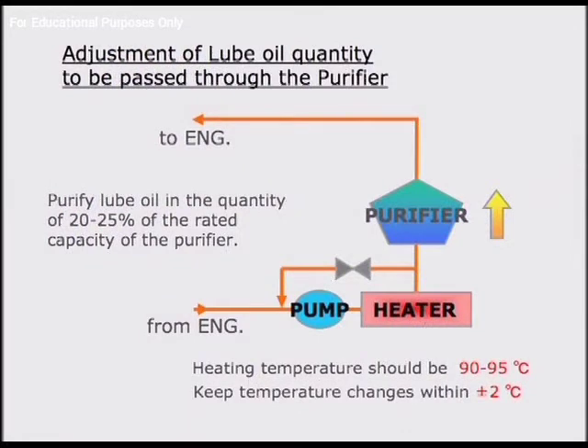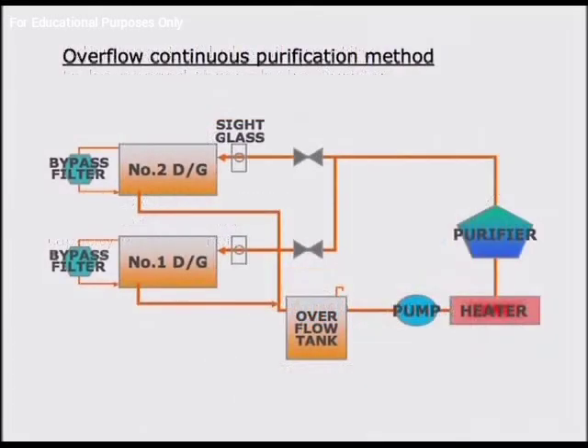Conduct the cleaning treatment with the feeding oil quantity covering 20 to 25 percent of the rating capacity of the purifier. Set the heating temperature at 90 to 95 degrees centigrade and keep the temperature variation within plus or minus two degrees. The continuous overflow cleaning method allows you to curb the dirt level of the lube oil to a certain level.